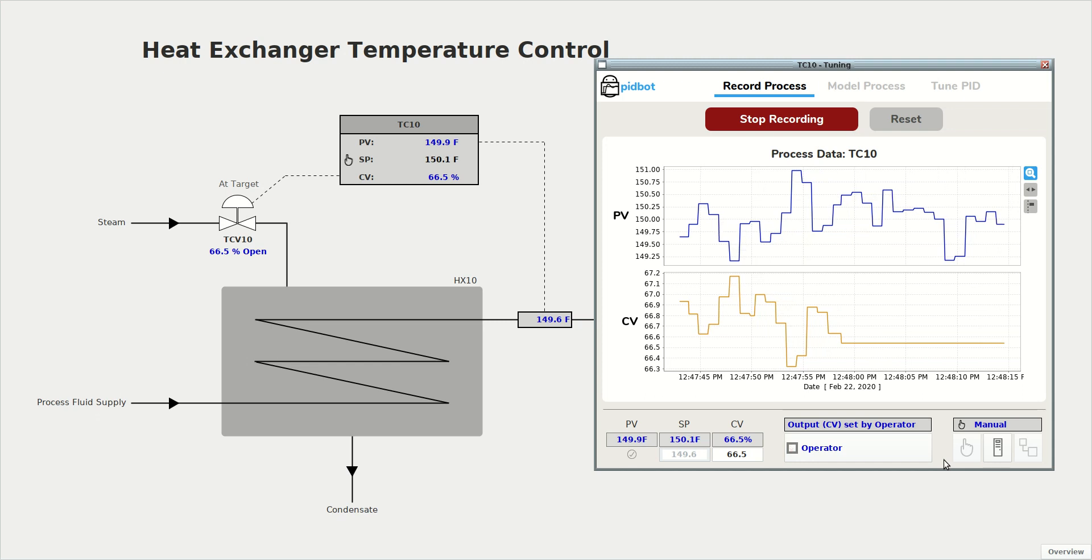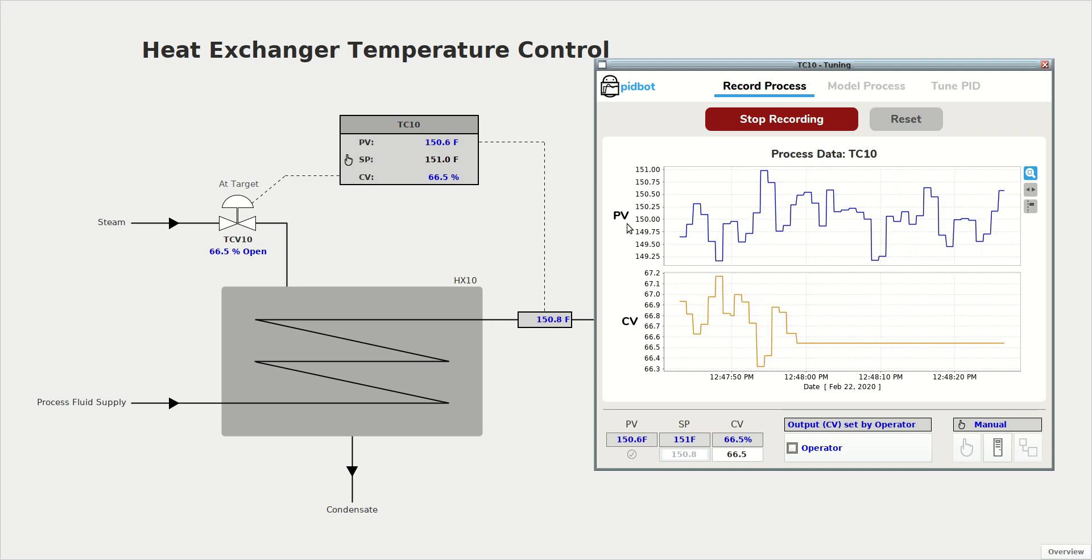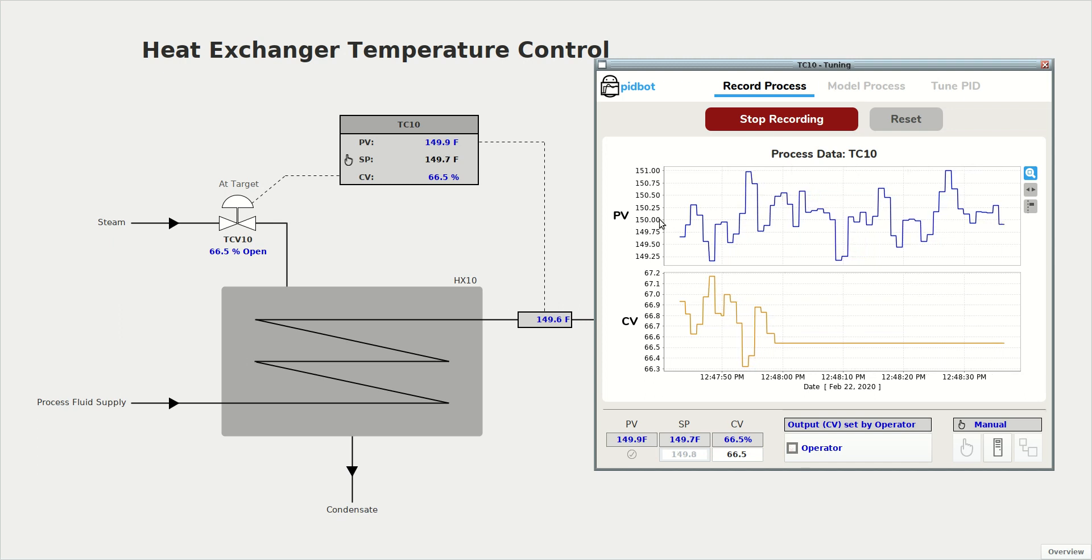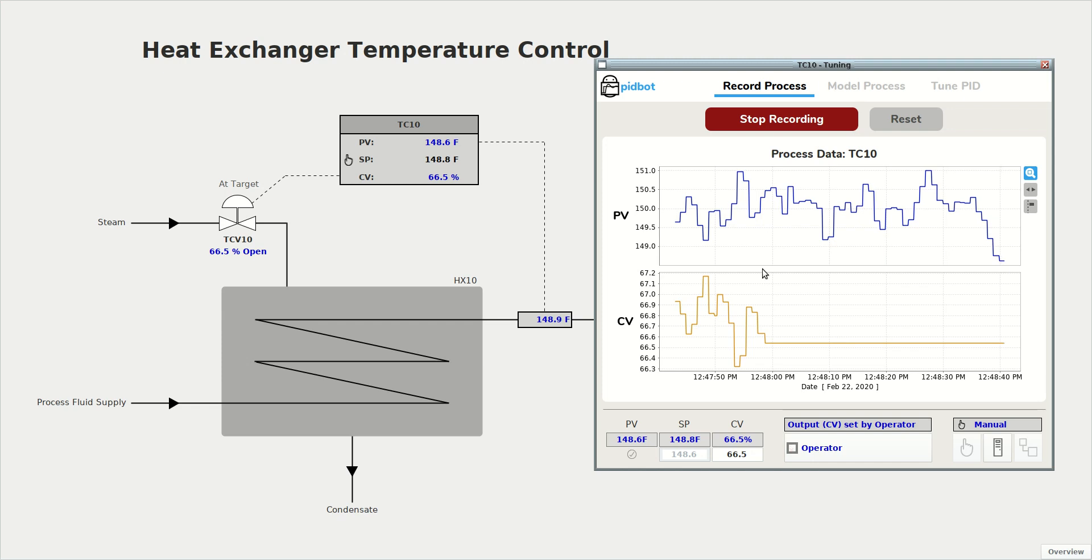It's got a little bit of noise in temperature, but the process itself is pretty steady. And you also want to make sure that you're doing your test at the normal operating condition of your process. In our case, we typically control around 150 degrees. So we're already at our normal operating condition and our process is nice and steady.